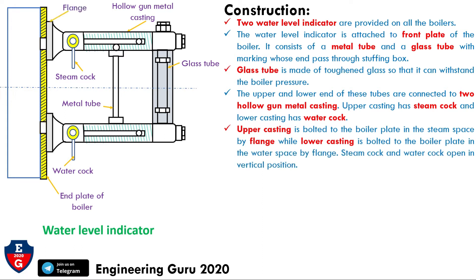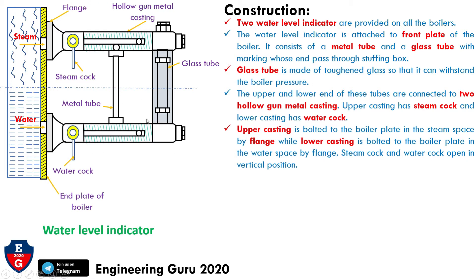The upper casting is bolted to the boiler plate in the steam space by a flange, while the lower casting is bolted to the boiler plate in the water space by a flange. The steam cock and water cock open in the vertical position. This flange is for the upper side and this flange is for the lower side. Here, this is the water-entering area and this is the steam-entering area.